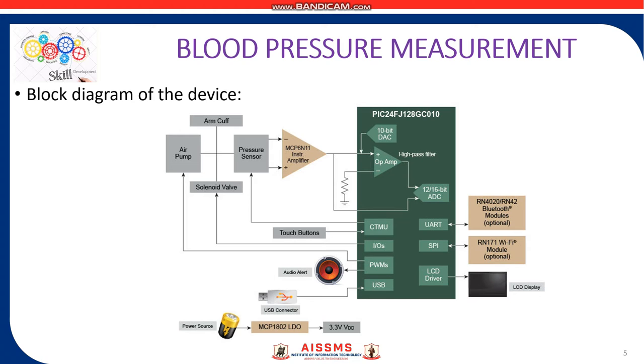For user interface, most blood pressure monitors employ an LCD. A high-end blood pressure monitor may use a color LCD with a touch screen to implement an advanced user interface. Audible notifications in blood pressure monitors can be provided by simple beepers driven by one or two microcontroller port pins that have PWM capability. More advanced voice announcements can be achieved by adding a DAC and an amplified speaker.